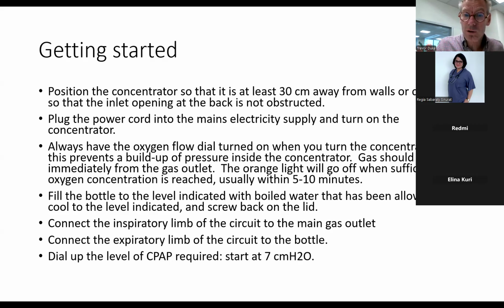So you want to use sterile water or cool boiled water, not hot water, and screw the lid back on, of course. You connect the inspiratory limb of the circuit to the gas flow outlet on the concentrator, and then the expiratory limb of the circuit is connected to the bottle, so the child can exhale into the bottle, and that will generate the CPAP.